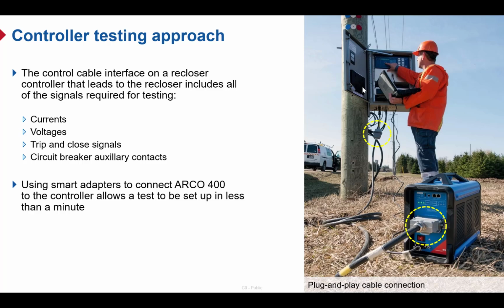During testing, we connect the ARCO 400 directly to the interface using smart adapters. This makes the setup very fast and simple. In most cases, it takes less than a minute to get ready. Another practical advantage is flexibility in the field. The ARCO 400 can even be powered using an inverter connected to a car battery, converting 12-volt DC to 220-volt AC. This makes it very useful for remote locations where no direct power source is available.